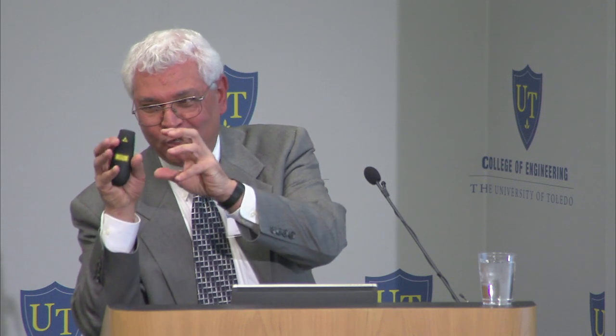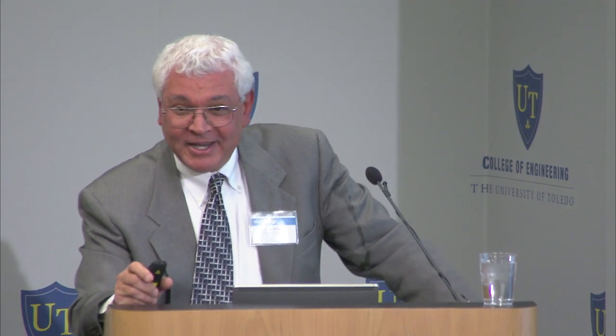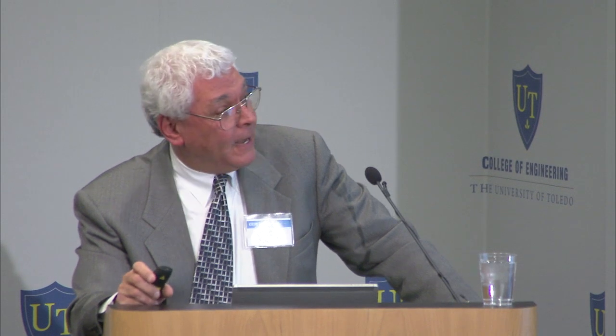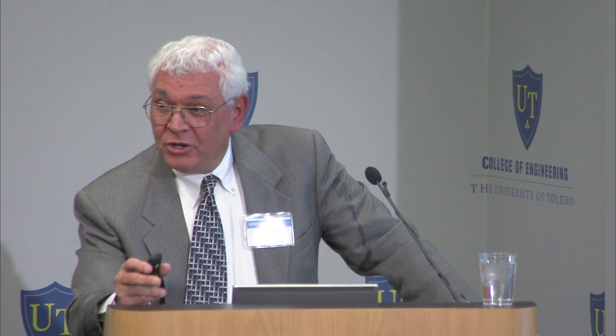The thermodynamic worth of that amount of heat exported, or the economic worth of that heat exported, is not the same. So even though in kilowatt hours they numerically have the same number, their utility — economists use a concept called utility — their utility is completely different. So we had to define modifications of the ERE that take into account the difference in either the thermodynamic worth or the economic worth of that amount of heat exported.